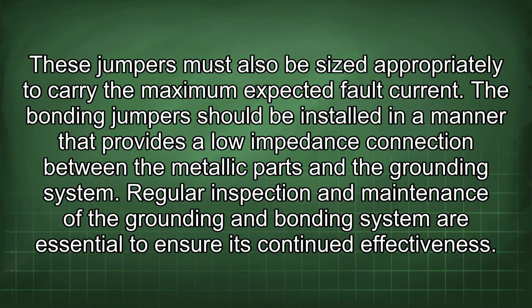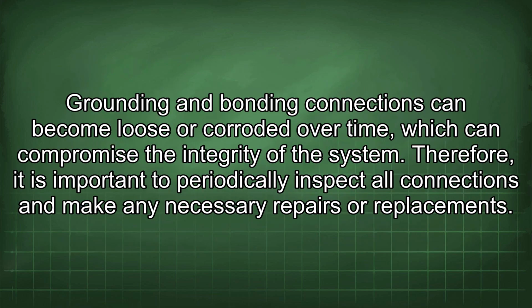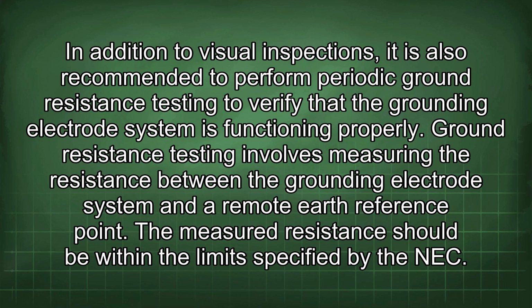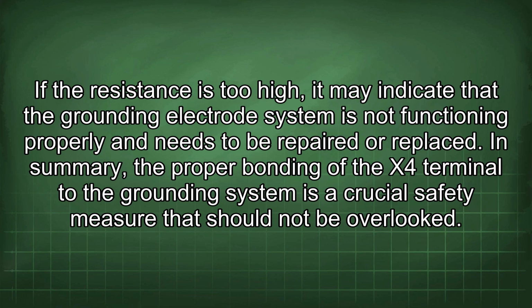Regular inspection and maintenance of the grounding and bonding system are essential to ensure its continued effectiveness. Grounding and bonding connections can become loose or corroded over time, which can compromise the integrity of the system. Therefore, it is important to periodically inspect all connections and make any necessary repairs or replacements. In addition to visual inspections, it is also recommended to perform periodic ground resistance testing to verify that the grounding electrode system is functioning properly. Ground resistance testing involves measuring the resistance between the grounding electrode system and a remote earth reference point. The measured resistance should be within the limits specified by the NEC. If the resistance is too high, it may indicate that the grounding electrode system is not functioning properly and needs to be repaired or replaced.